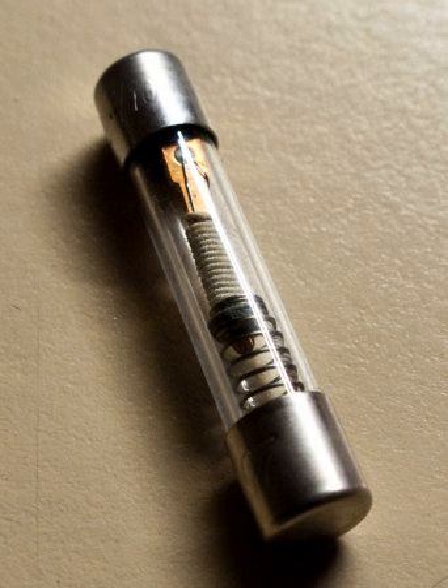Conventional designs as high-performance fuses permit safe disconnection of residual currents up to 120 kA rated breaking capacity, whereby the rated current can be up to 1.6 kA. HRC fuses are widely used in industrial installations and are also used in the public power grid, e.g. in transformer stations, main distribution boards, or in building junction boxes and as meter fuses.